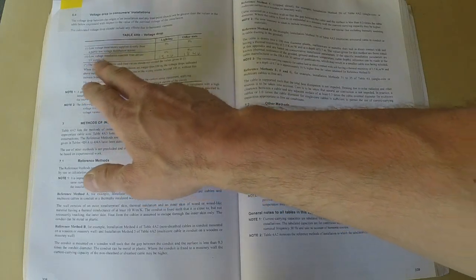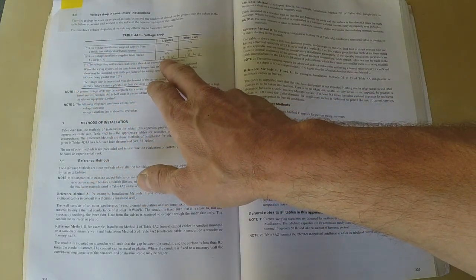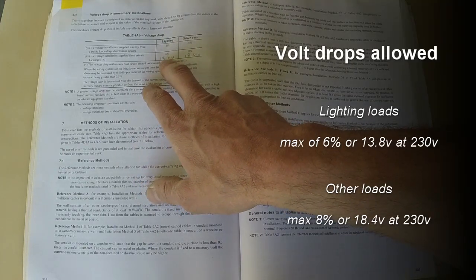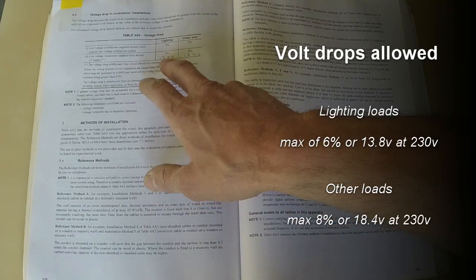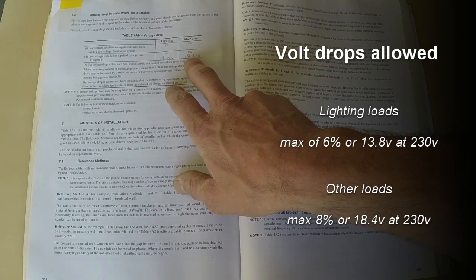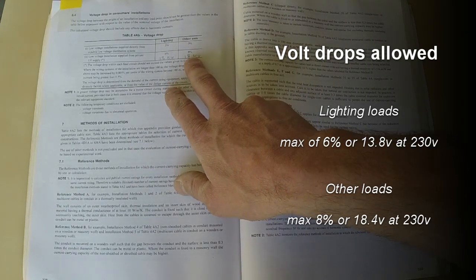For lighting that's 6%, which is 13.8 volts allowed at 230 volts, and 8% for all other uses, which is 18.4 volts.